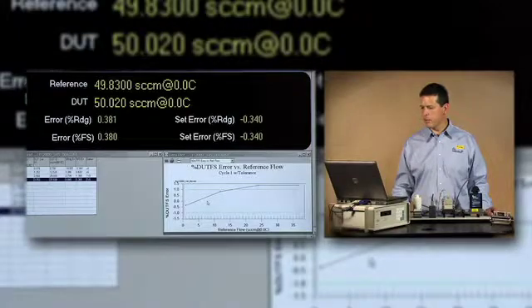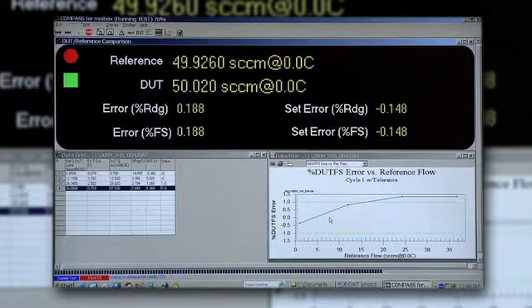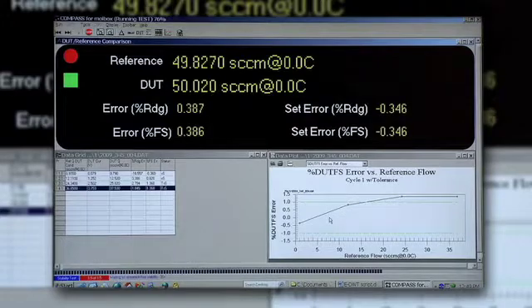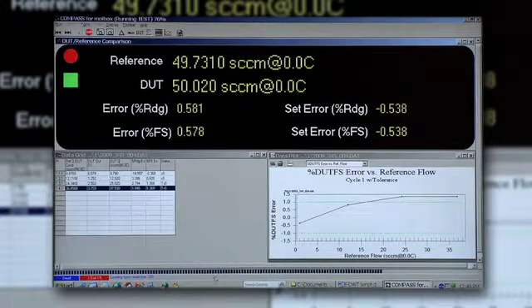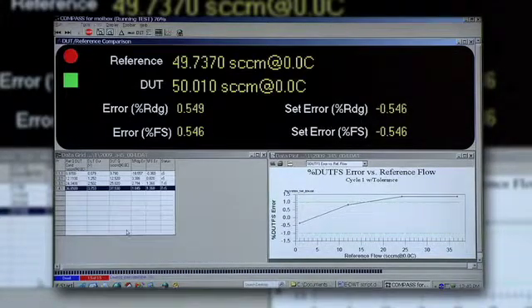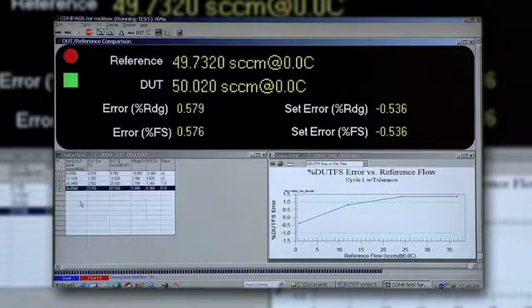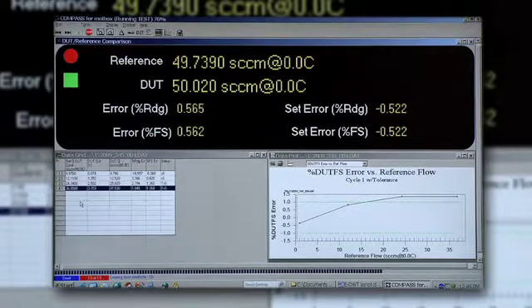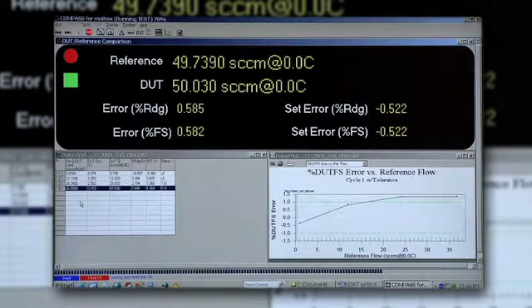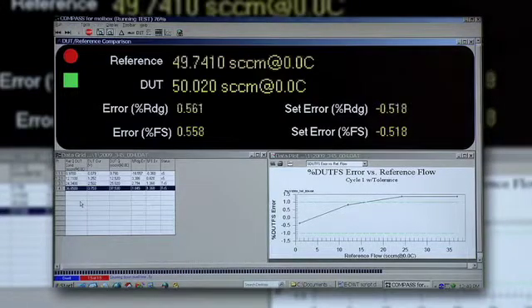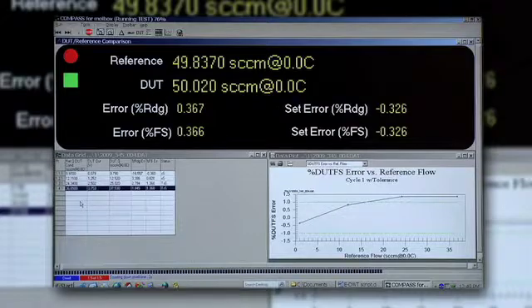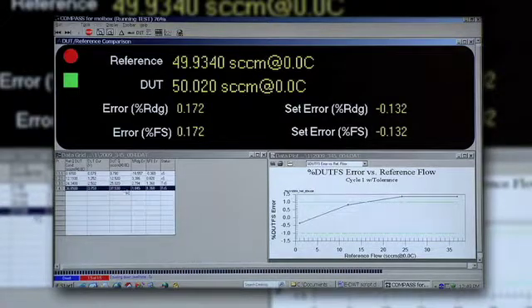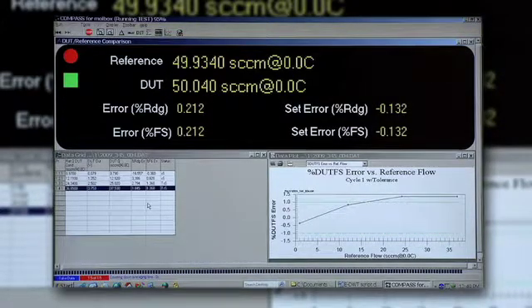We have one more data point which is now being collected. At the moment we're waiting for flow stability which is indicated on the progress bar at the bottom of your screen. Note on the lower left in your data grid you have just some of the data that's being collected by Compass. There's a lot more points being collected here that can be used in the data report later but it does show the output of both the device under test and the reference molbloc on each point. It indicates whether flow is stable and shows both the percent of reading and percent full scale error.